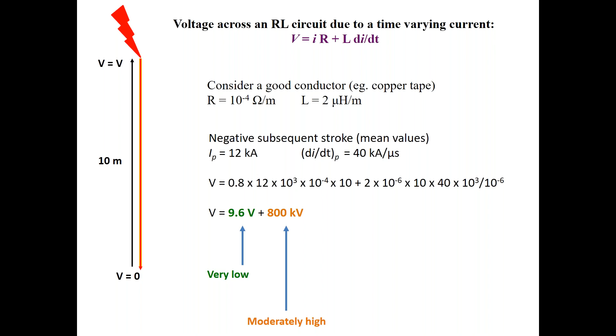This is something that you should not forget, because when you are designing a lightning protection system, make sure that you have an understanding. Even with a copper conductor at a 10-meter height, you can have something like 800 kV, or at 1 meter 80 kilovolts. Don't forget that this is for the mean value, not extreme values. So the actual value in some cases of lightning can be much higher.